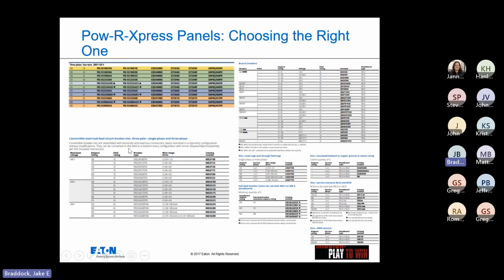And so here, I know it's probably hard to see some of this, but basically these are the different catalog numbers that Shaler can get in stock and how they would build your panel. So for instance, if you're looking for a 225 amp aluminum panel main breaker with, let's just say, 10 single pole 20 amp breakers, right? What would happen is Shaler would have this aluminum interior right here. So they would have this interior in stock. It's 42 circuits, 225 amps, three phase. And then this is the tub for it, and then this is the trim for it. And then we also actually have a NEMA 3R tub available too.